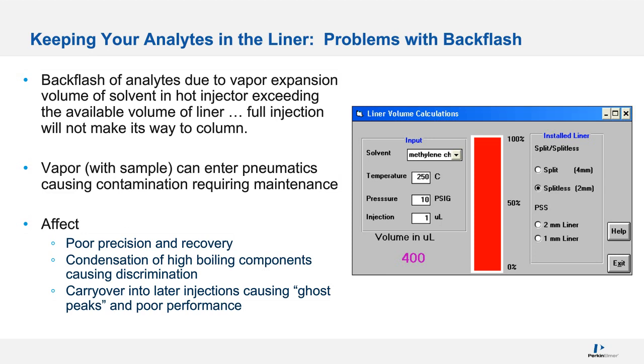High boilers could condense at the top, because the injector is not as hot on the top as it is in the center. It could flash back into the pneumatics, depending on how much vapor expansion, and then that's a service problem, right? Unless you change your own pneumatics. But the biggest thing is we're going to have poor precision and poor recovery. We could lose our high boilers, giving us poor recovery and discrimination across our target range. Also, we could get carryover into later injections, causing ghost peaks, because a lot of times ghost peaks are peaks that are not nice and Gaussian because they've been hanging around. They broaden out and can interfere with your targets in the next injection.